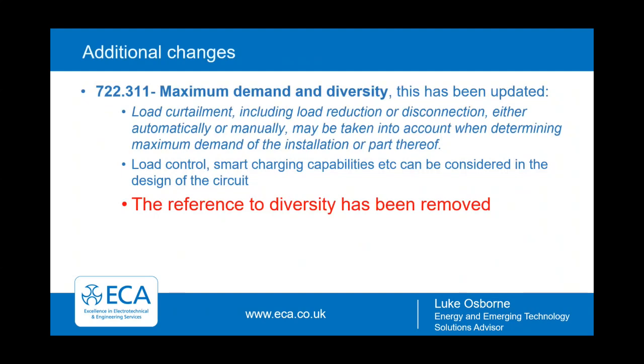There's a couple of additional changes. 722.311, this pertains to maximum demand and diversity. It's quite important to note that the reference to diversity has been removed apart from in that title.